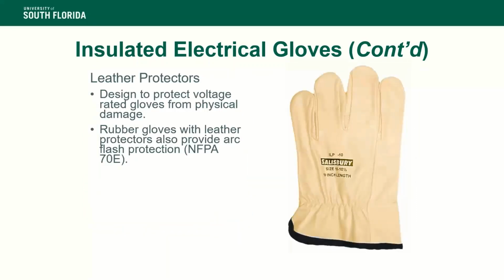Here's another one we look for: leather gloves. The leather gloves have to be designed to protect the voltage-rated rubber gloves from physical damage. These go on the outer part of the rubber gloves, but you have to make sure the technicians know how to put them on properly so they don't cause problems when using them. So outside of this, make sure that when you give them the PPE, you're also training them on it.